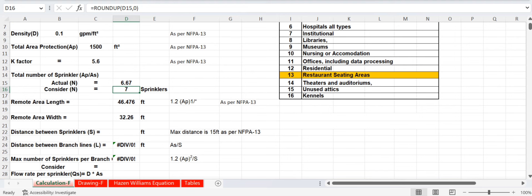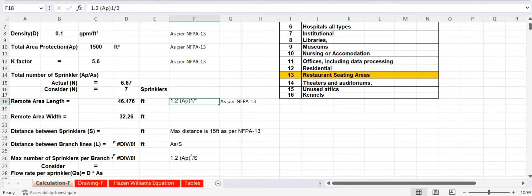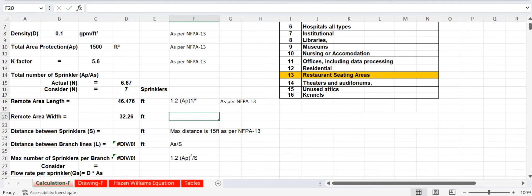To calculate the remote area length, the formula is 1.2 × √AP, where AP is the total area protection of 1500 square feet. Applying this gives a remote area length of 46.476 feet.